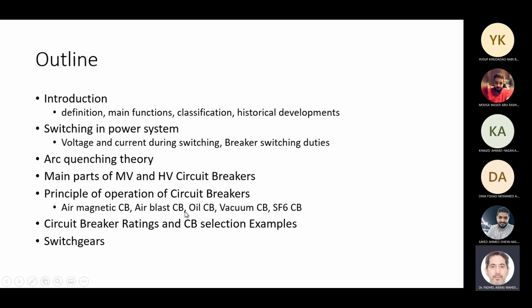But I will not cover breakers that are obsolete now, like the oil circuit breaker. It's not used anymore, so I don't want to cover it. But we'll cover breakers like vacuum and SF6. And then we'll go over the electrical specifications that an electrical engineer needs to know about circuit breakers. Now, how do you choose a circuit breaker that will be able to break a short circuit current? I'll show you some examples if possible, and we'll define what a switchgear is, inshallah. What is the difference between a distribution board, a switchboard, a switchgear, and so forth.